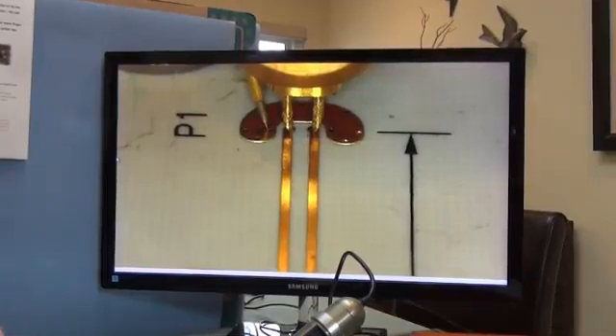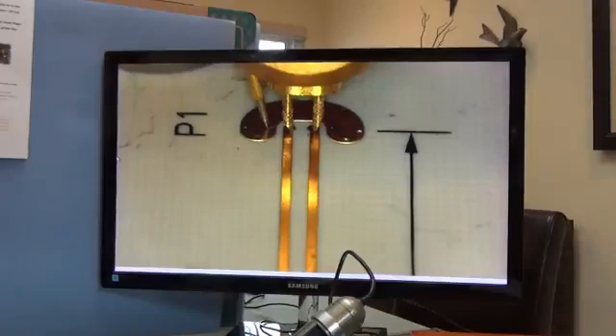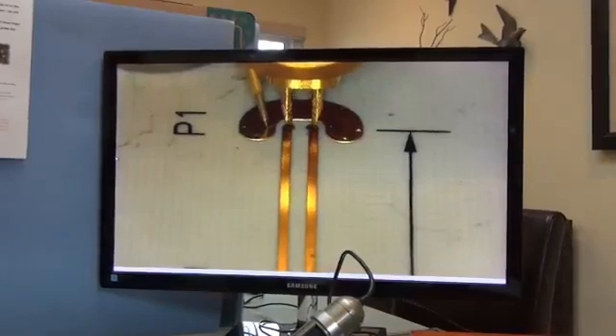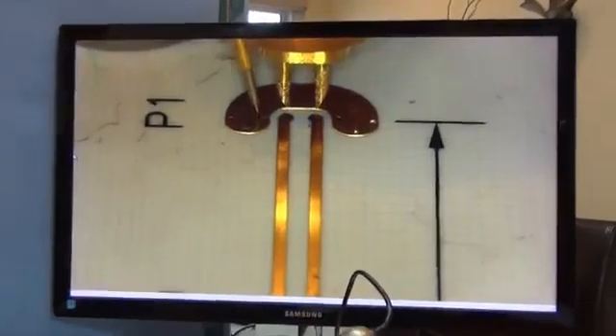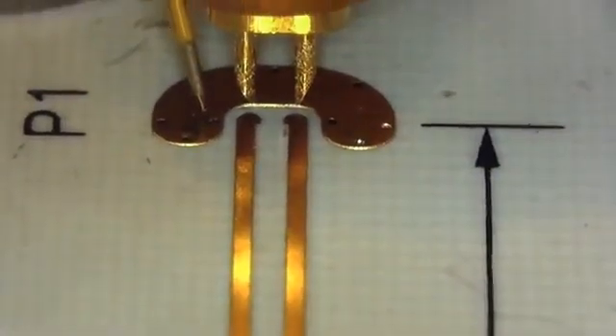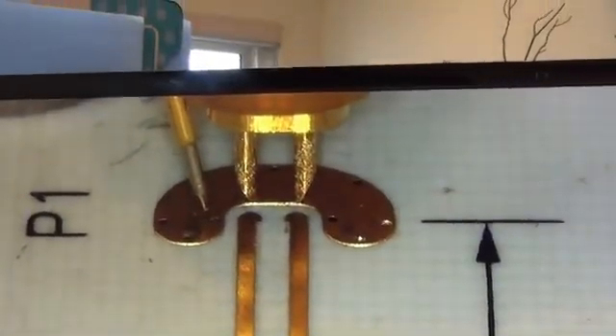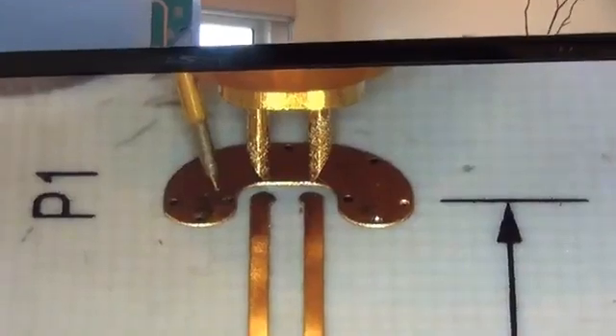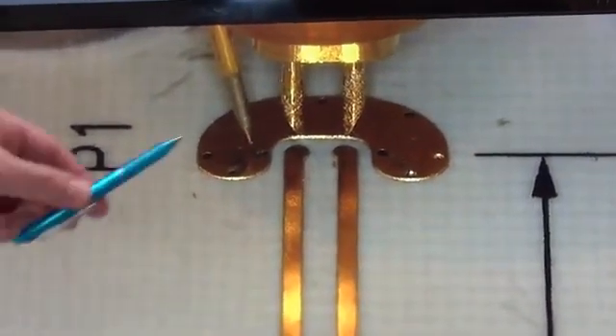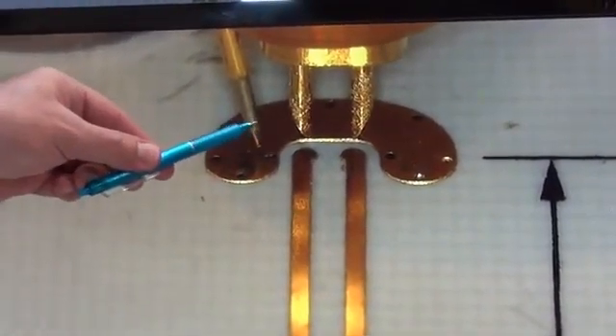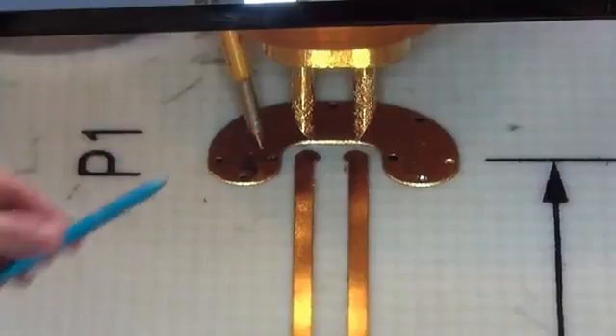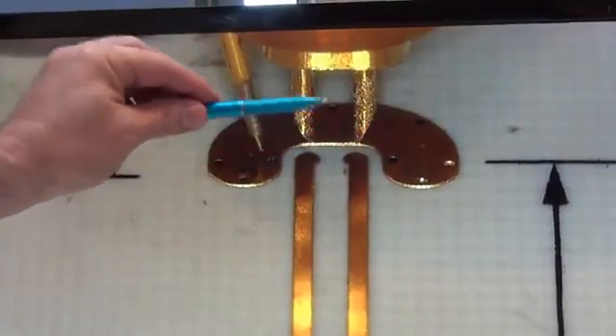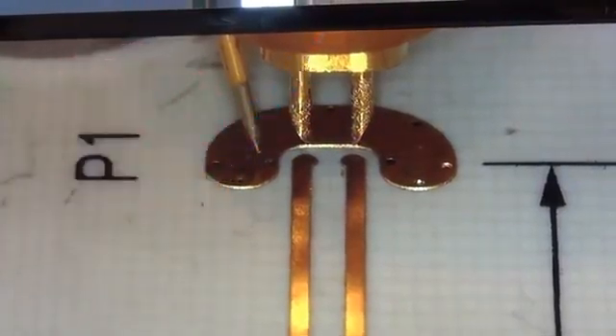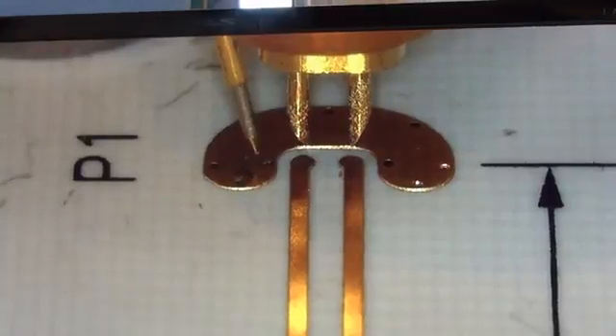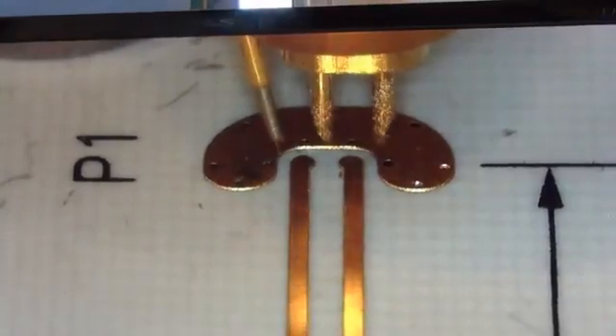So first thing you want to do is bring up the probe tips, so both the probe tips and the ground clear the test pads. Next thing I want to do is, since this one here is the one that's not making contact, I want to move it off in this direction, so I move this side down. And I do that by adjusting the theta control.